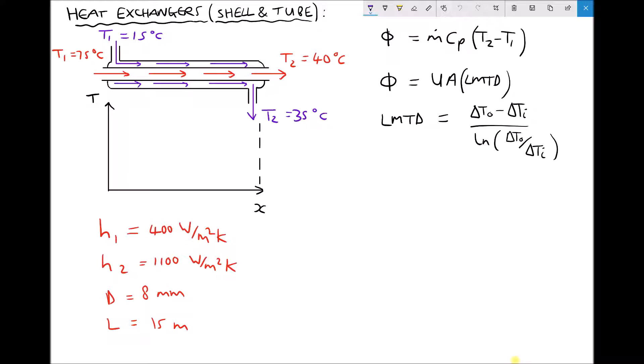We have our two surface heat transfer coefficients, the diameter of the tube, and the length of the tube. Note that we only have one diameter and one length — that's for the tube running through the centre, because the contact surface area between the two fluids is the outside surface of that tube. The diameter of the shell is irrelevant because contact between the two fluids occurs at the surface of the tube.